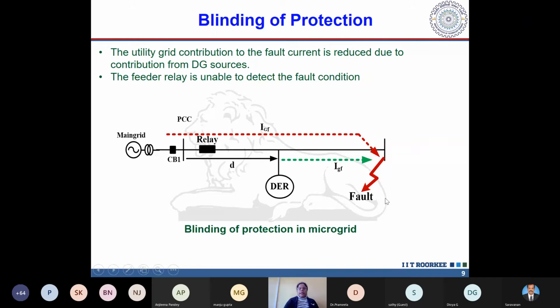So in this kind of situation, what will happen? Let us say your fault current remains constant because the fault path remains constant. This fault current is a combination of two fault currents: one by the grid and another by the DER. The resultant of these two fault currents is the total fault current.